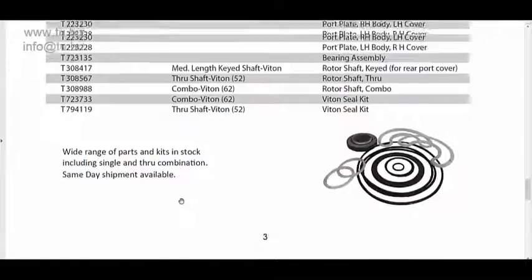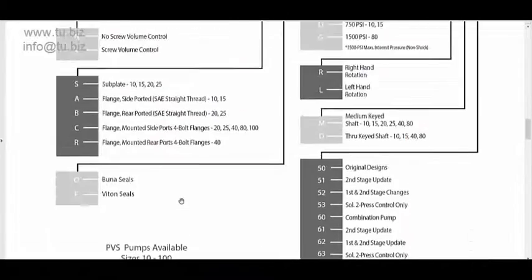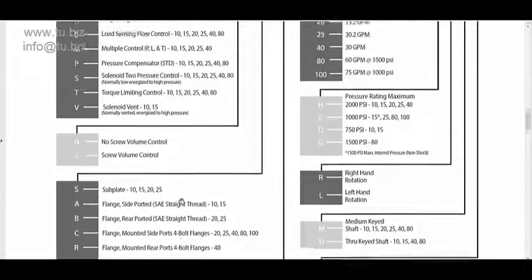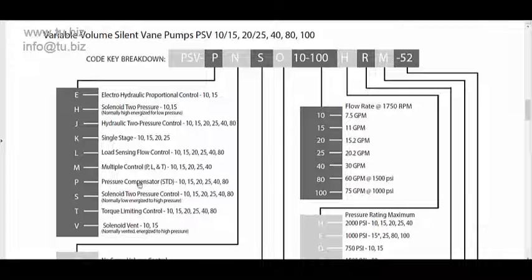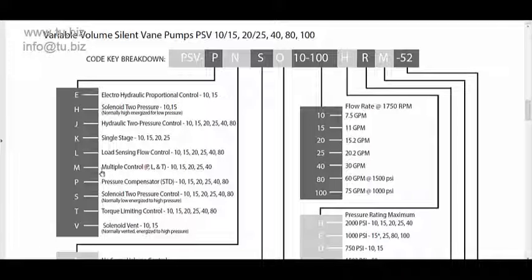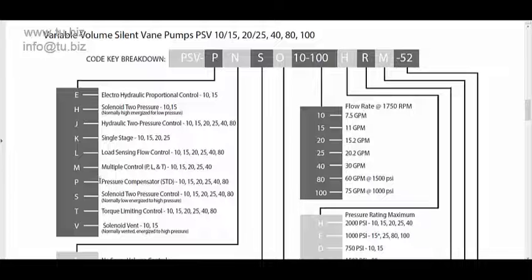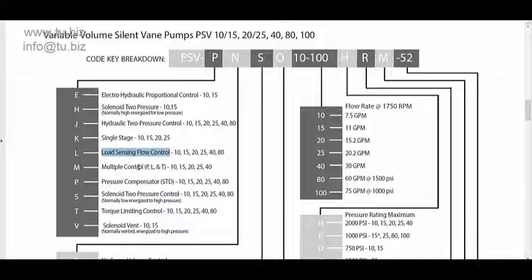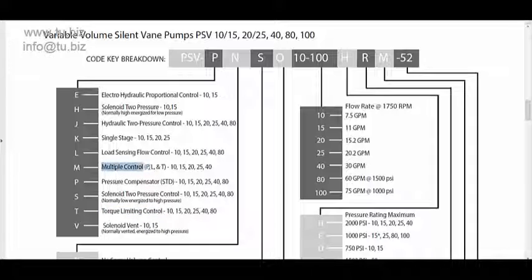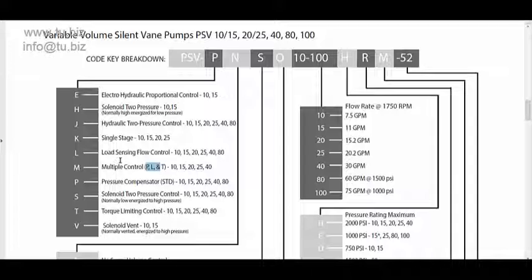Let's check out how to build a part number and reference for control for these units. We have the most important one, pressure compensated. Everybody always needs a pressure compensated control. That means when the pressure goes up and reaches a certain level, the pump is going to destroke and sends no pressure. That's variable displacement pressure compensated, the most standard control. Then you have the load sensing control, torque limiter, and then you can have the combination of those three with the multiple control that includes P, L, and T, which is the load sensing pressure control and the torque.